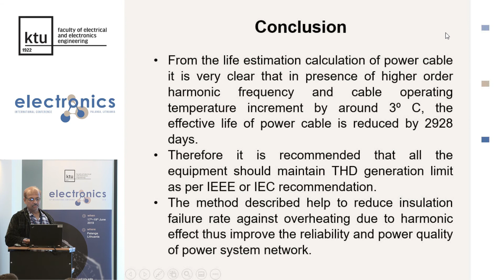You talk about 3,000 days, the decreasing of effective lifespan. What is the nominal lifespan of this cable? Normal lifespan of a power cable is basically 15 to 20 years, or 25 years, depending on the voltage gradient. For high tension cables used in mines, even 6.6 kV cables are used, and there the lifespan is more or less 18 to 20 years. Out of that 20 years, if it is used for 4, 10, or 5 years, that will be deducted from the lifespan, so it will directly affect your economy and investment.